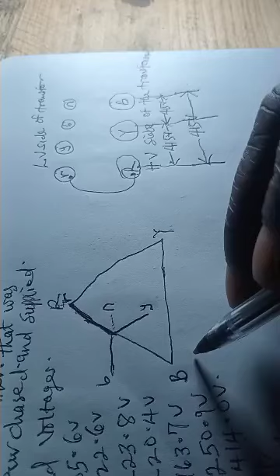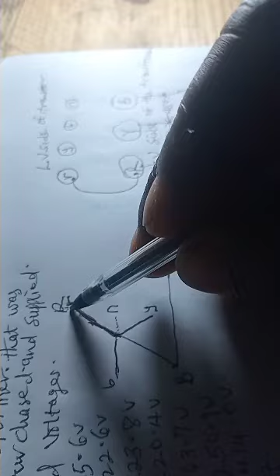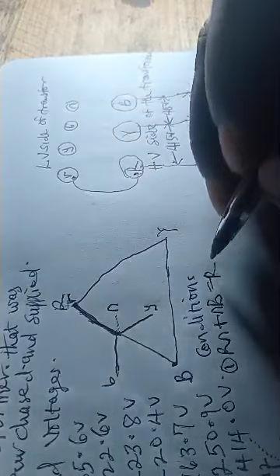Now, you take your measurements after the derivation. So look at here. The first condition, if we measure between here and here, then between here and here, we also measure between here and here. See how it goes. First condition, condition 1. You measure between red to neutral plus neutral to blue, equal to red to blue.